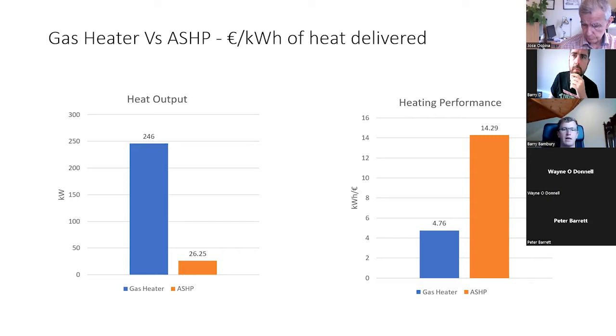Then we look at the air source heat pump, completely the other end of the spectrum. What we found is that the heat pump, when it was in use, very rarely stayed at its rated output. It cycled. It might turn off for 10 minutes every hour. We saw over the course of 4 hours, typically it would consume 30 kilowatts of electricity. So per hour, that's €1.79. So this gas heater is consuming 52 euros per hour, and this air source heat pump is only consuming €1.79 per hour.